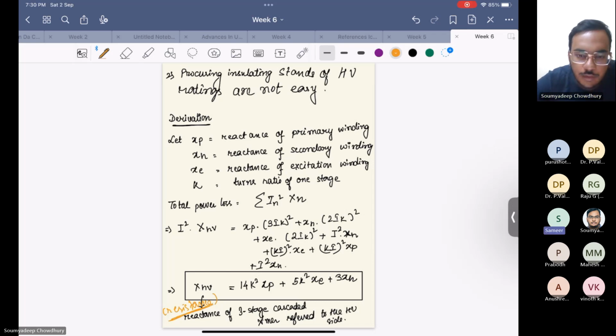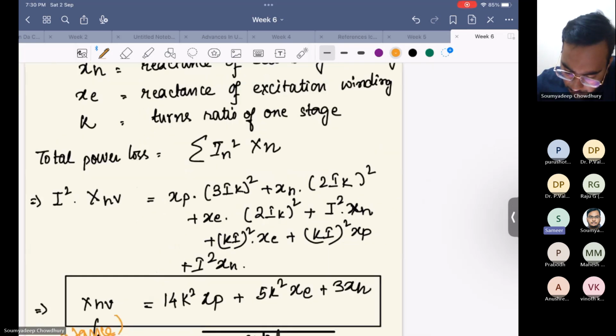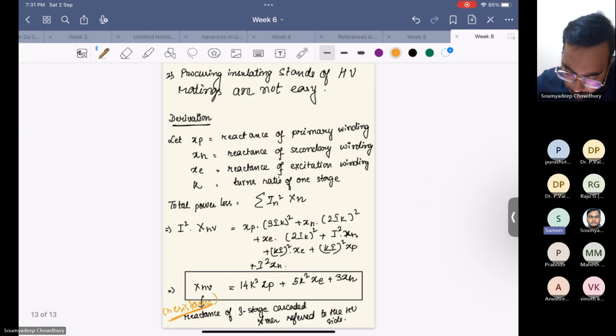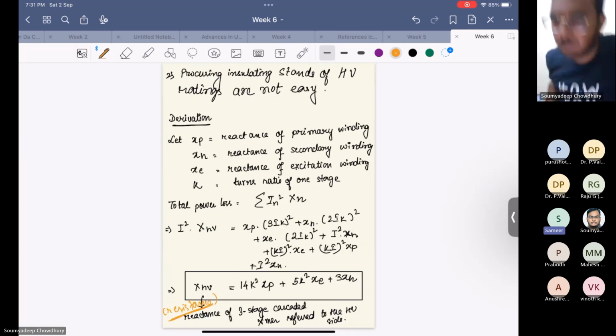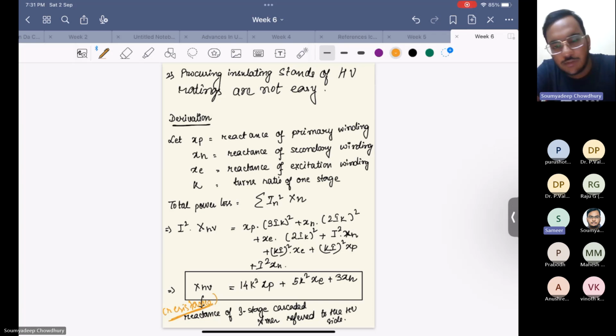Sir, I was going through the weekly course. It is mentioned that the circuit breaker has the property of detecting a fault. Can you please elaborate? Because as far as I know or have seen practically, CTs and VTs are the devices which detect the fault and they relay it to the circuit breaker for tripping. Your voice was breaking in between, can you tell the first line once again?